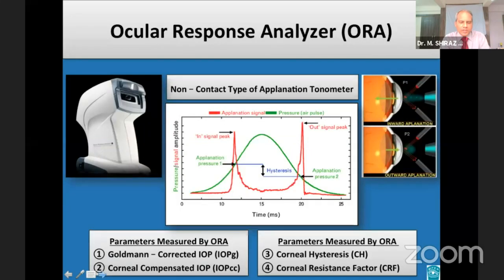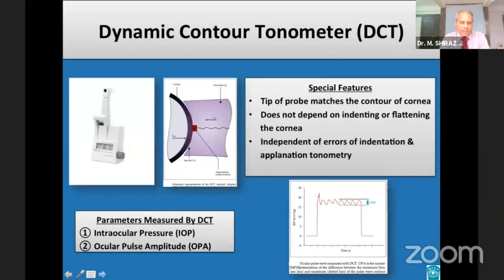The Ocular Response Analyzer uses a rapid air pulse to record two applanation pressures — one while the cornea is moving inwards during applanation and the second while the cornea is moving outwards while recovering. The average of the two gives Goldman-corrected IOP and the difference gives corneal hysteresis. In the Dynamic Contour Tonometer, the tip of the probe matches the contour of the cornea, eliminating the influences of corneal biomechanical factors. It measures IOP in both diastolic and systolic phases of the cardiac cycle, and the difference is called the ocular pulse amplitude.